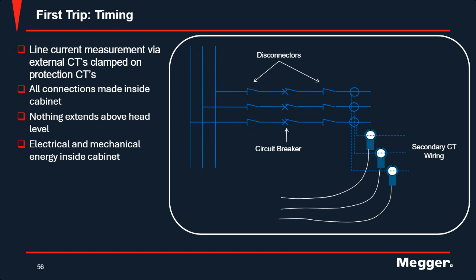Now, if you wanted to do timing, all you would need is three more CTs. They will go on the secondary line of the CTs of the circuit breaker. When the breaker is open, the current stops and the CTs stop reading. Your secondary wiring will no longer have current on it, and your CTs will notice that and stop the timer. So based off the pulse from the switch house, and those secondary CTs no longer seeing current, it can time your breaker. Again, there's no need to go to the overhead level. All this is done from inside the control cabinet of your circuit breaker.